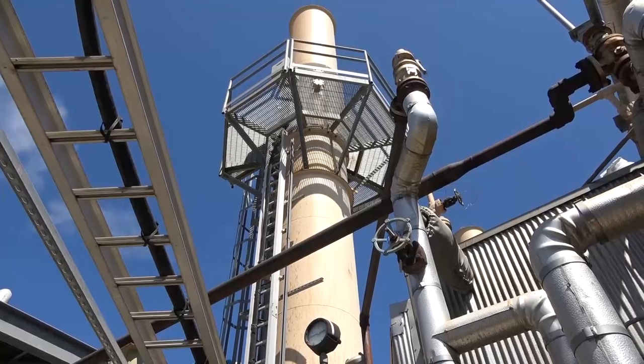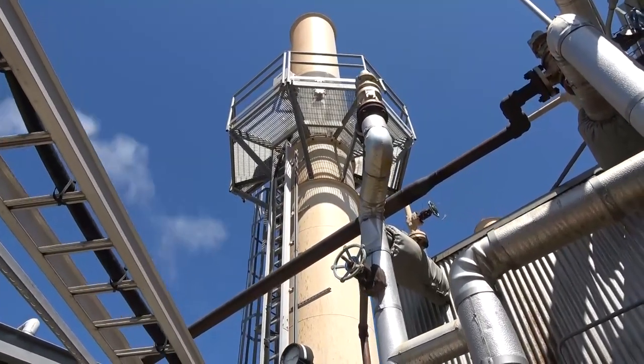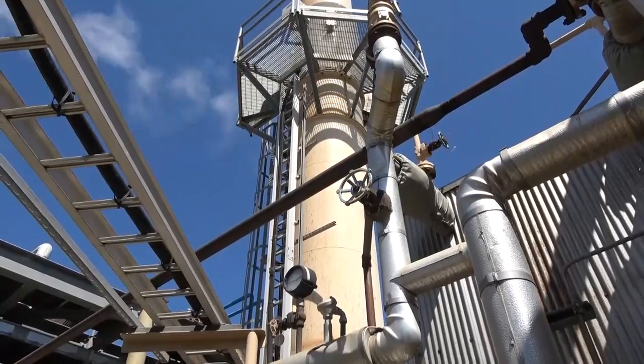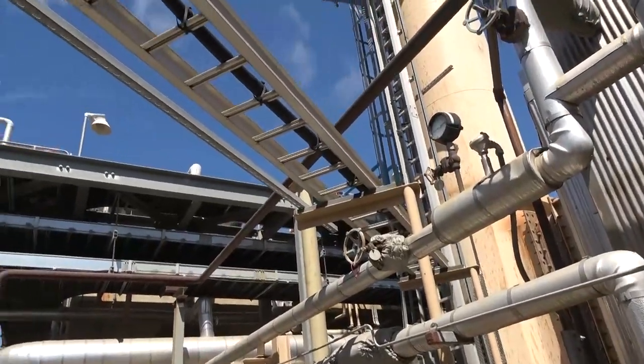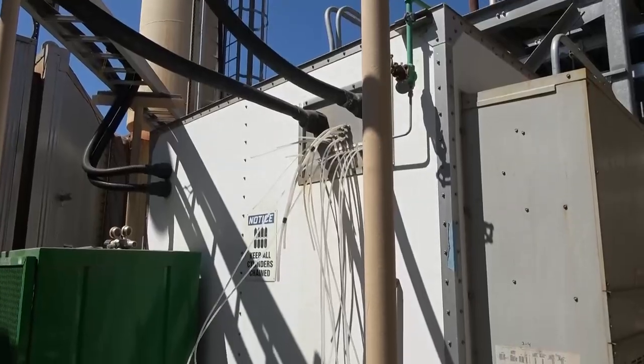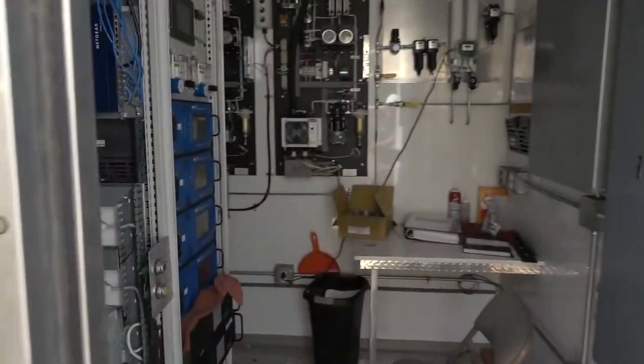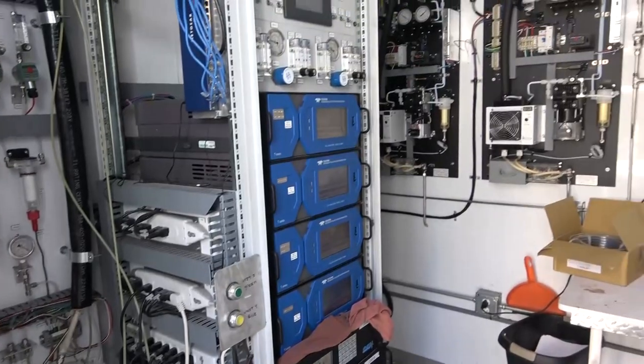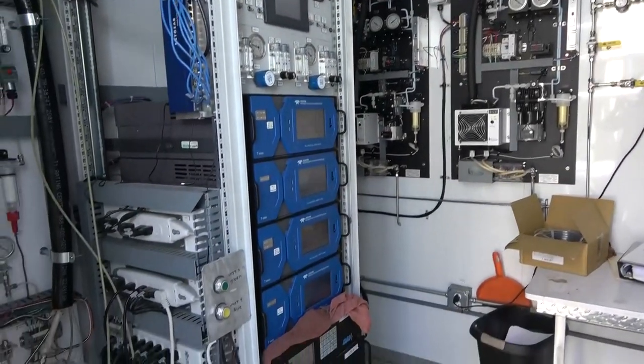Like all plants in Southern California, emissions must be continuously monitored and sent in real time to the South Coast Air Quality Management District. The large black insulated sample lines come off the very top of each stack, join together from this four-unit plant, and go right into the emissions monitoring building. Inside, you can see all the sampling lines, processors, and computers — each monitoring for NOx, carbon monoxide, or unburned hydrocarbons.